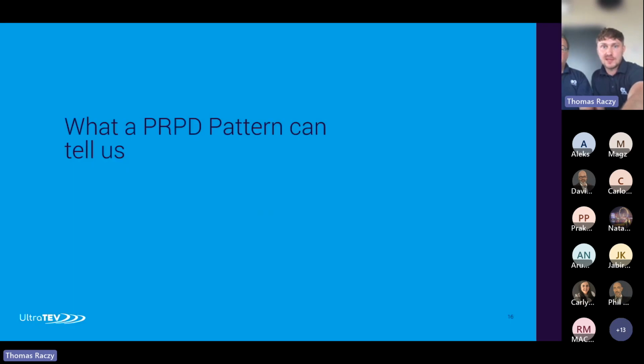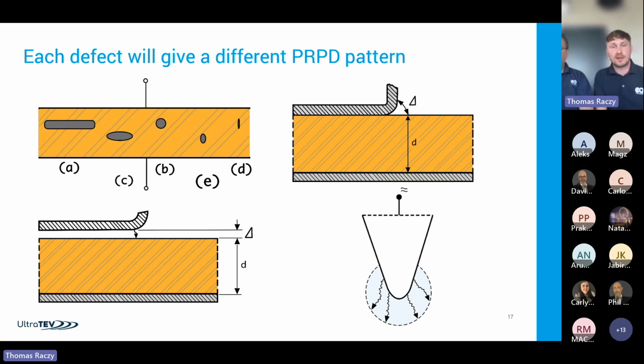So what can the PRPD pattern tell us? Each internal defect inside the insulation, depending on the actual shape of the defect, might produce different phase resolved patterns. It also depends on whether the defect is closer to the conductor or the screen, which again ends up with a different phase pattern. For surface discharges, it depends whether it's a discharge across the surface towards the ground, as in the top right corner, or a discharge across a gap; that again will end up with different phase resolved patterns. Corona discharge, bottom right corner, is typically from a sharp edge at high voltage, and because there's only one electrode involved in that discharge, typically there's only one group of discharges across the power cycle.